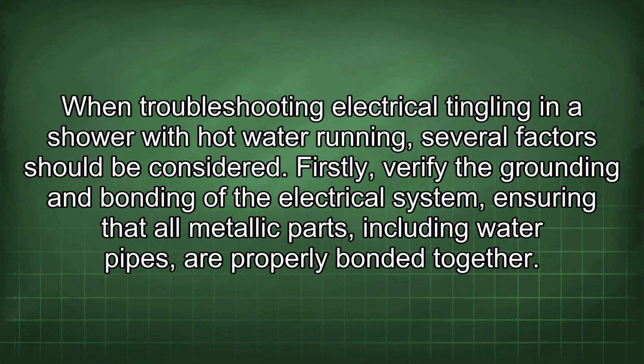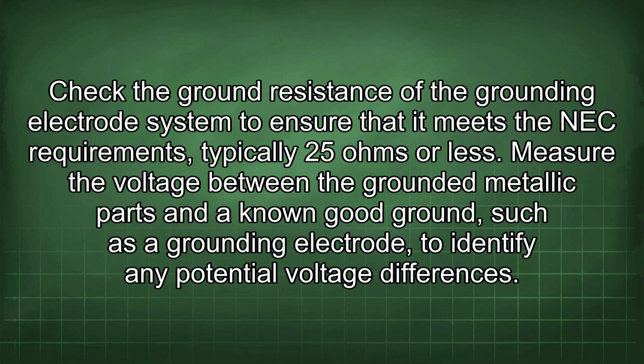When troubleshooting electrical tingling in a shower with hot water running, several factors should be considered. Firstly, verify the grounding and bonding of the electrical system, ensuring that all metallic parts, including water pipes, are properly bonded together. Check the ground resistance of the grounding electrode system to ensure that it meets the NEC requirements, typically 25 ohms or less. Measure the voltage between the grounded metallic parts and a known good ground, such as a grounding electrode, to identify any potential voltage differences.